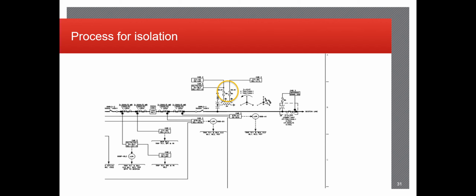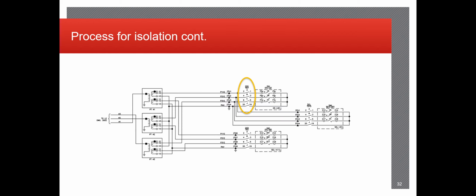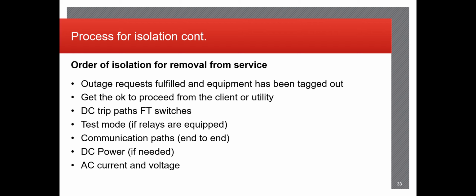We're pointing out the CCVT fuses here that show the voltages that are going into the existing relays, as well as the 3-line schematic for the voltages. For the process of isolation, you definitely want to identify your current and voltage sources first and understand that they are coming from the correct piece of equipment to the correct relays that you're going to be isolating. That's what we're doing here.